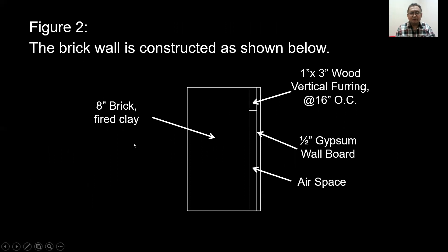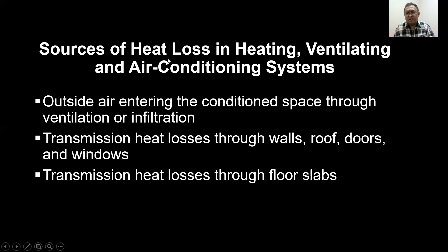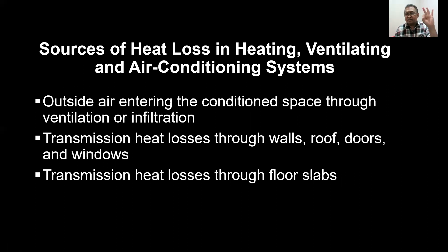The brick wall is shown below. You have 8 inch brick made of fire clay, 1 by 3 inch wood vertical furring at 16 inch on centers, half inch gypsum wall board, and an air space. The sources of heat loss in heating, ventilating, and air conditioning systems are: outside air entering the conditioned space through ventilation and infiltration; transmission heat losses through walls, roof, doors, and windows; and transmission heat losses through floor slabs.